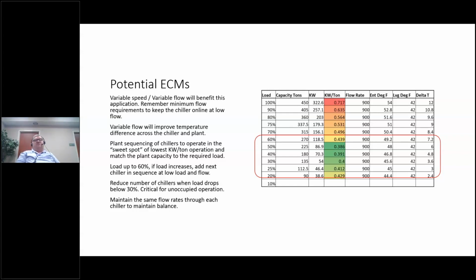Then there's plant sequencing of chillers to operate in this sweet spot of the lowest kilowatt per ton operation and match the plant capacity to the required load. You're trying to match your energy expended to the load required. Load up to 60%. If the load increases, add the next chiller in sequence. It's going to drop your capacity per machine, but the total capacity matches your load. But now we're operating at a more efficient point.